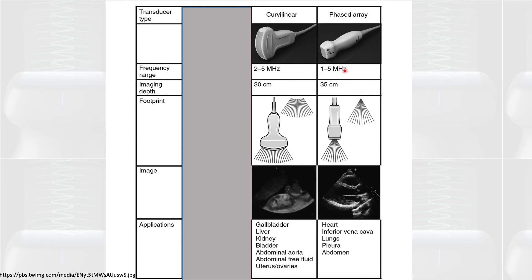The other two probes are low-frequency probes. Because of their lower frequency, they can penetrate much deeper — up to 30 or 35 centimeters. The cardiac or phased array probe emits beams from one point, which is advantageous for looking at the heart because you can get the beams between the ribs. The curvilinear probe, also known as the abdominal probe, is the classic one used for examination of abdominal organs.